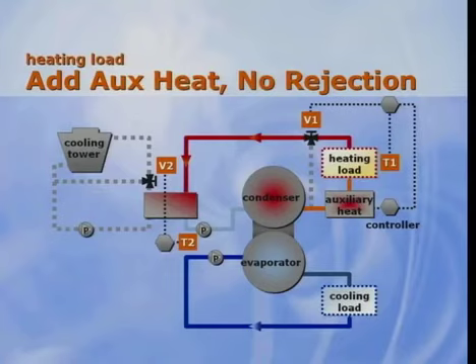This strategy should be used for heat recovery systems that are using entering condenser water temperature as the control signal. This is almost always used for centrifugal chiller applications in order to avoid surge, and can also be used for positive displacement chillers. However, there are some applications in which a constant leaving condenser water temperature is desired. In such a case, the control for centrifugal chillers is different than for positive displacement chillers.